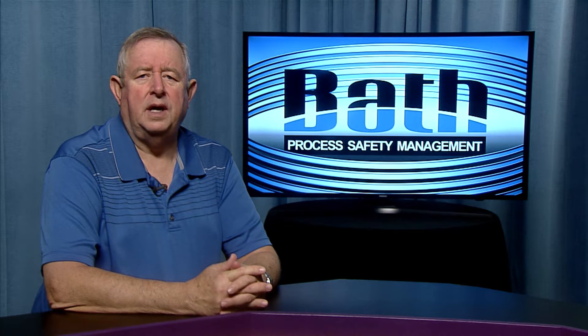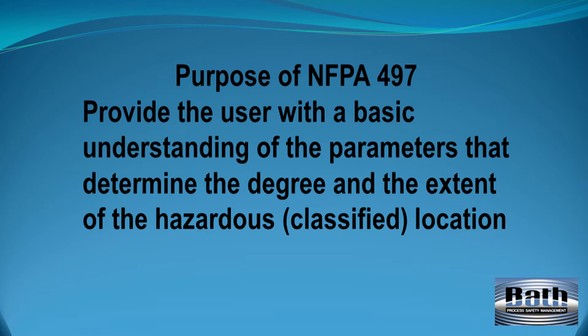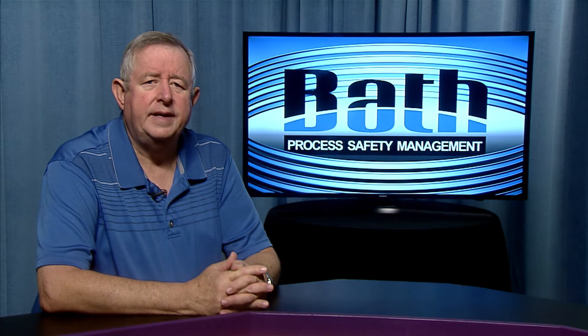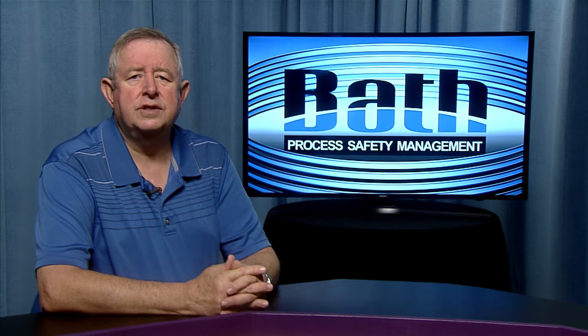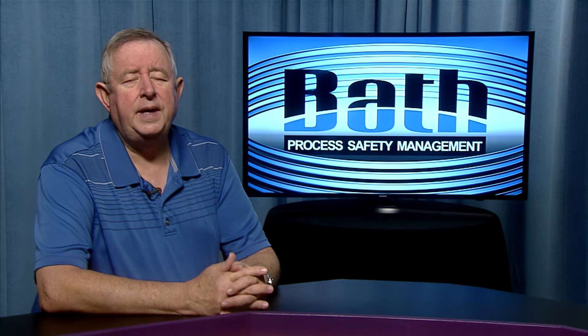Aside from the differences mentioned above, the purpose of these two documents is the same. The purpose of NFPA-497, as stated in Section 1.2 under the heading Purpose, is to provide the user with a basic understanding of the parameters that define the degree and extent of the hazardous classified location. This recommended practice also provides examples of the applications of these parameters, per Section 1.1.2 under scope, to allow classification into the groups established by NFPA-70, the National Electrical Code, known as the NEC, for proper selection of electrical equipment in hazardous classified locations.